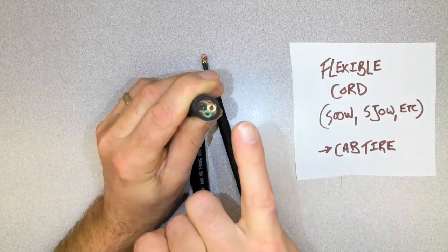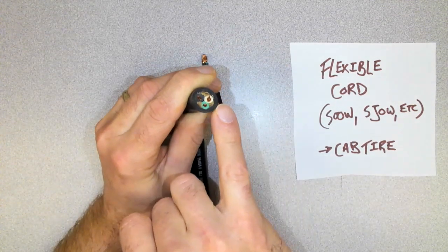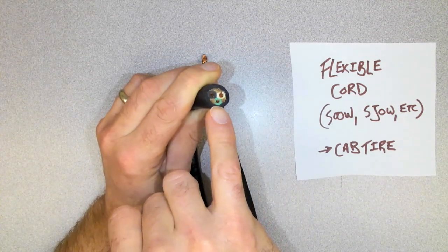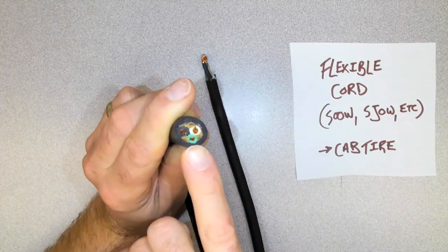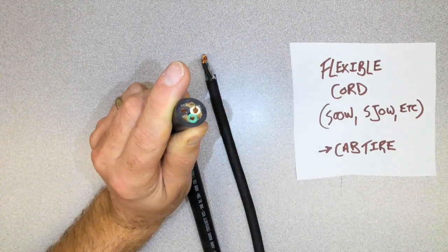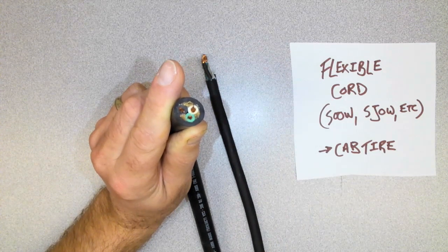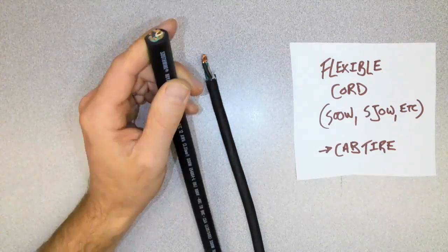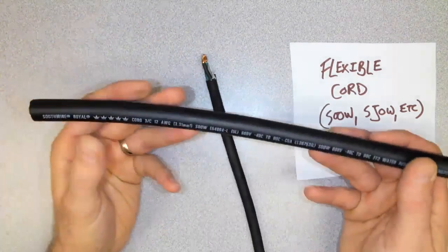Usually there's no space in between the individual conductors and the rubber jacket, and the conductor inside that's the bond is insulated. And so that means for this particular cable, these are 12-gauge wires, and there are 3 insulated conductors. This would be known as 12-3 flexible cord. A little bit different than what we see with the residential non-metallic sheathed.